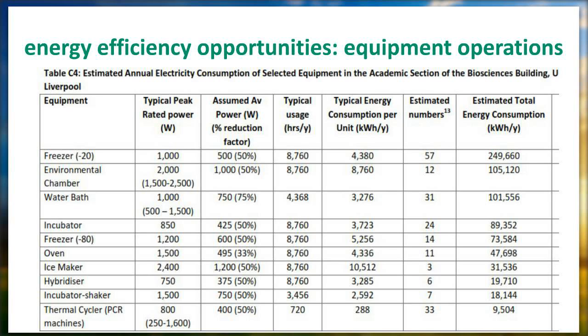If we look down here, water baths, which might not have been something on your radar before, they have 31 of them, and those use about 100,000 kilowatt hours a year, just in that one building alone. So I hope you can see that there's really some opportunity here based on what we know about typical energy consumption and typical hours of usage multiplied by the numbers of these types of equipment.